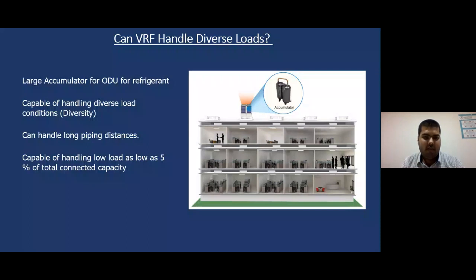Suppose I have filled 100 kgs of refrigerant in the entire VRF system. If only 6 to 7 kg is required, all the other refrigerant load would go to the accumulator and accumulate there, and only 6 to 7 kgs would flow through the entire system. So having an accumulator in a VRF is a must, and only then can it handle diverse loads.